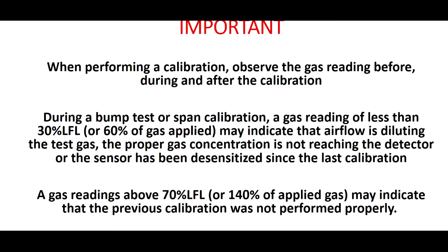It is important that when performing a calibration, you observe the gas reading before, during, and after the calibration. When the gas reading stabilizes, and if it's less than 60% of the test gas concentration being applied, this may indicate that airflow is diluting the test gas, the proper gas concentration is not reaching the detector, or the sensor has been desensitized since the last calibration.